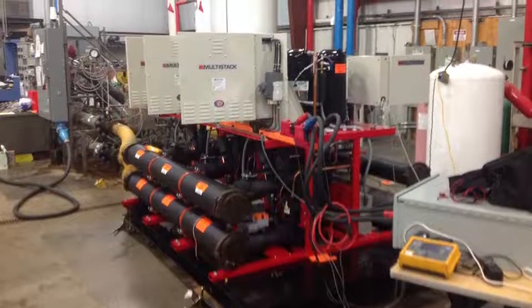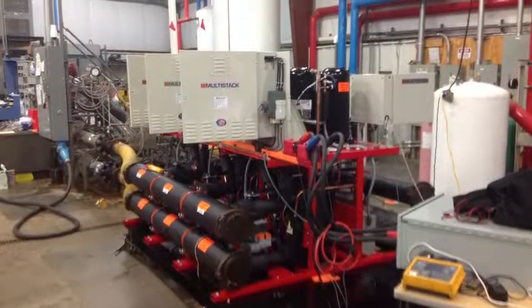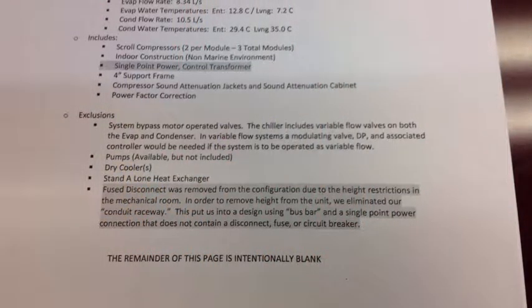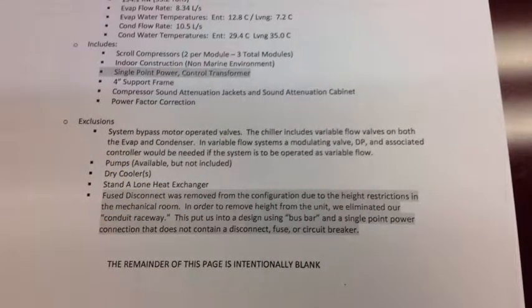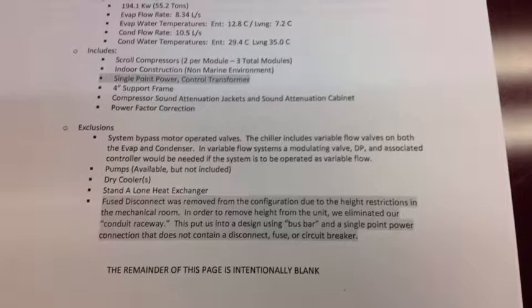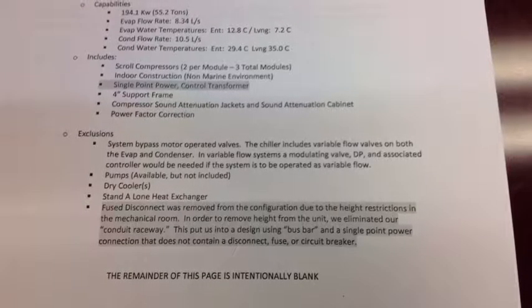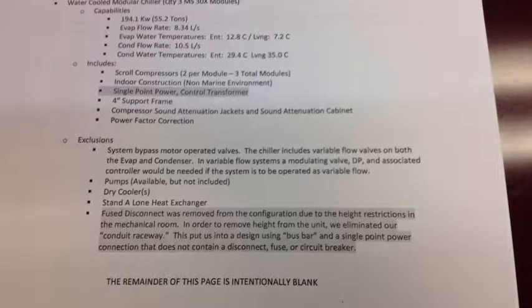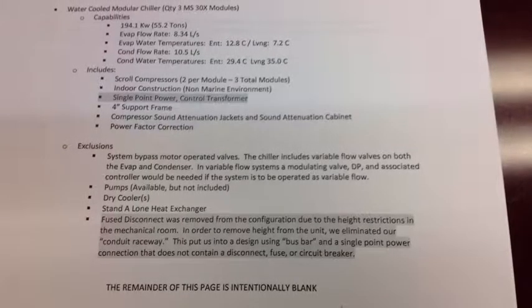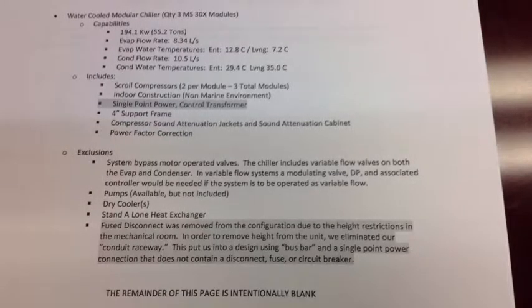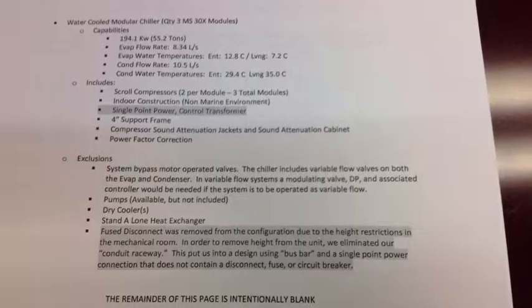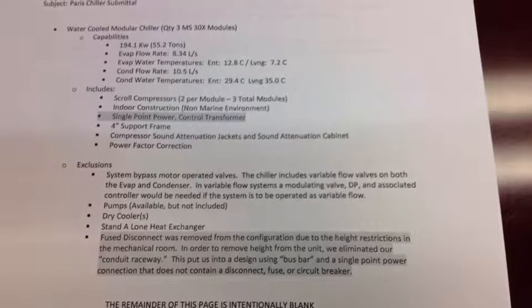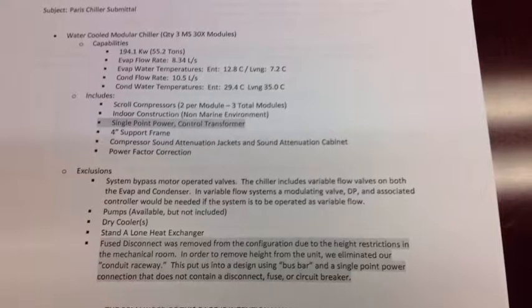We will be taking a tour during the witness test of the water-cooled chiller for your project. Here's a shot of our submittal. We will see the 2 scroll compressors, note the indoor construction, point out the single point power connection, the 4-inch support frame, talk about the compressor sound attenuation that will be added after the test, show you the power factor correction installed in each module.